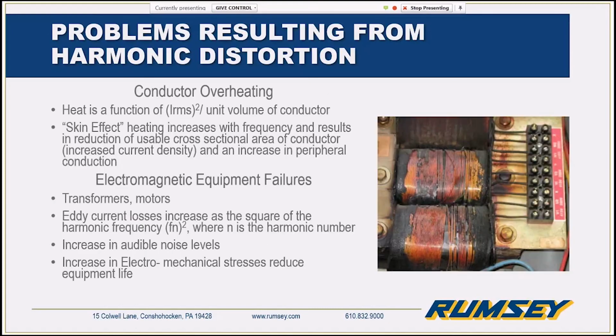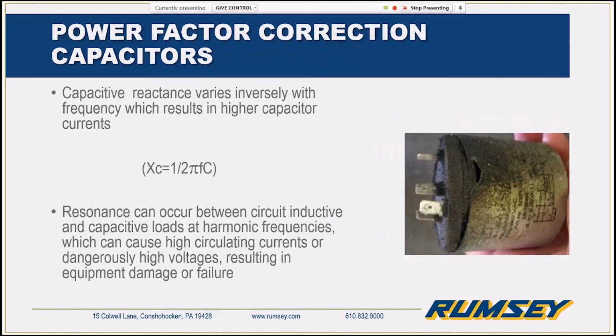And then, I already kind of mentioned this again, this will help to decrease your overall system capacity, because your transformer is designed to have a certain amount of current go through it, or the generator is designed to provide a certain amount of current, and now you're providing all of this reactive high frequency current that you weren't originally designed for. Additionally, we've seen a lot of applications where power factor correction capacitors have failed because of VFDs.